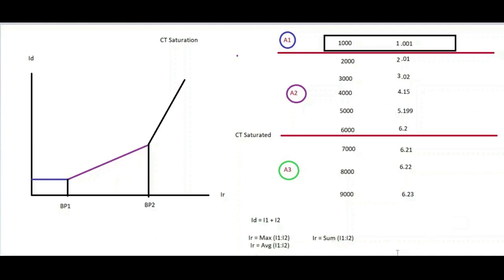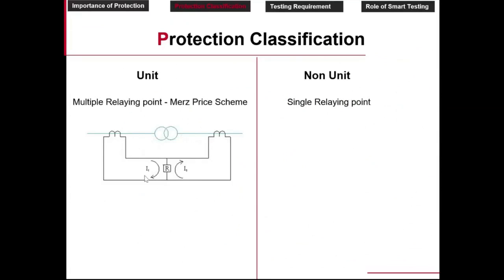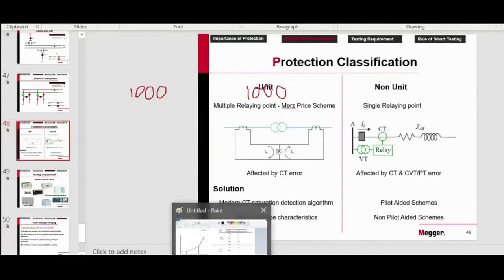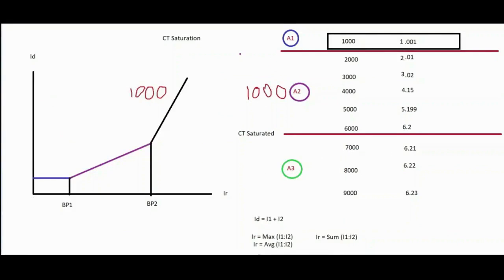Now you have a system like this. Let us say you have 1000 amps flowing here, and you have 1000 amps flowing here. Assume this is a transmission line, not a transformer, so that it's easy for us to calculate. So 1000 amps in the primary means 1 amp in the secondary, 1.001. So find out what your ID and IR are for each case.